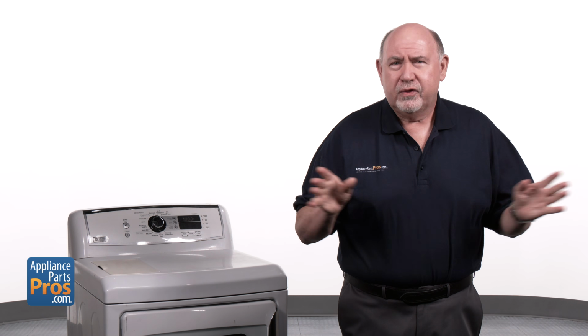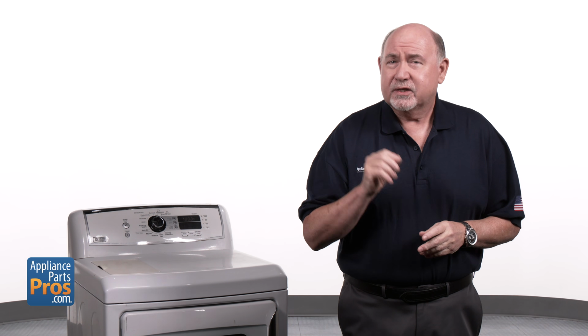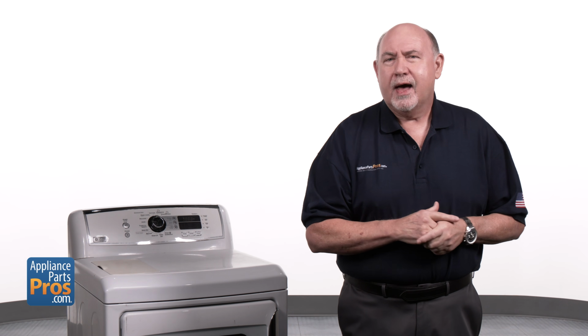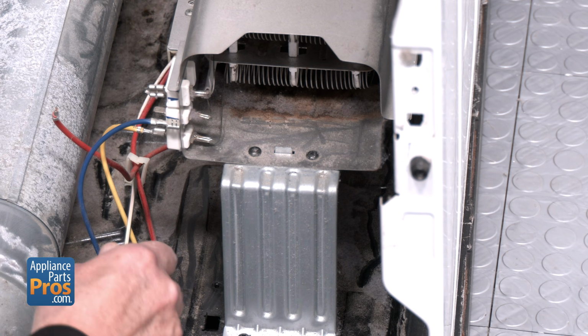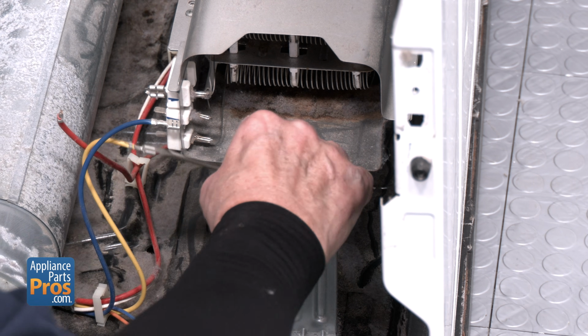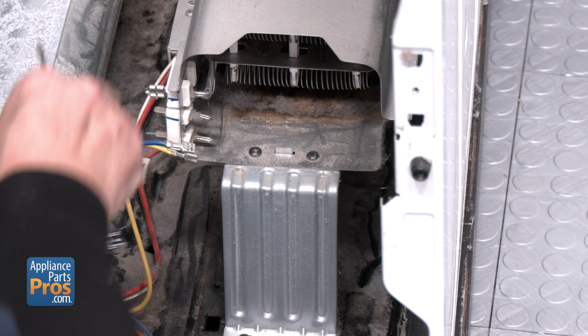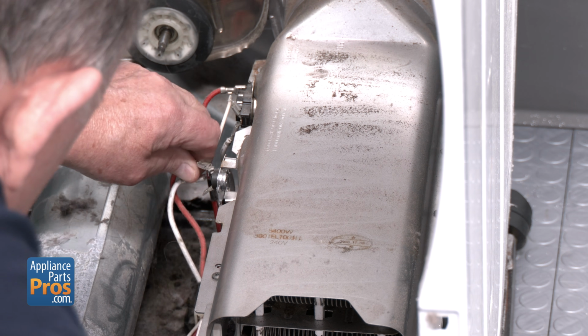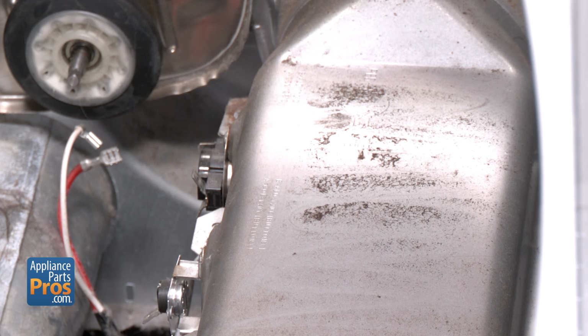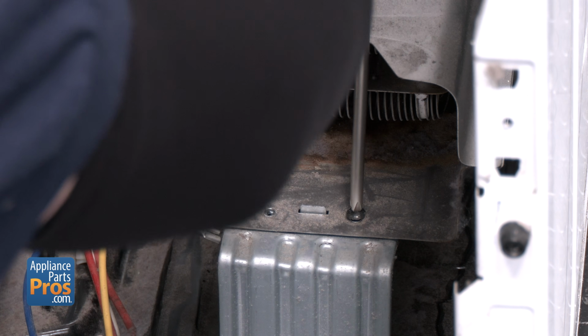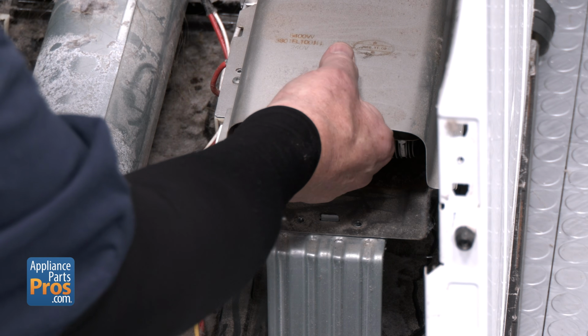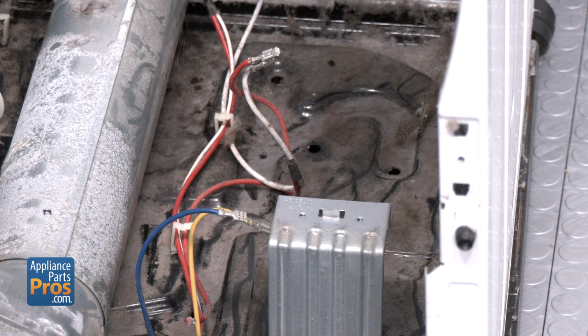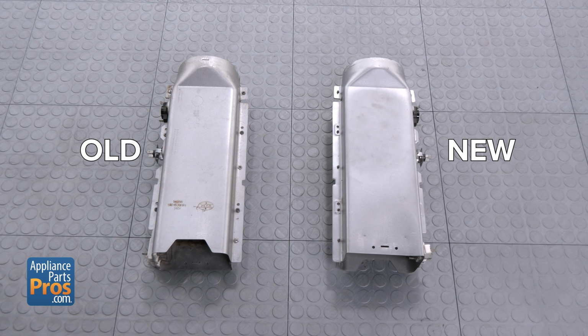After going through all the checks, we found the heating element itself had failed. Let me show you how to replace it. The heating element comes as a complete assembly with the high-limit thermostats already installed. Remove the wiring, take pictures if needed. Then remove the 2 screws in front. Lift up and remove the element assembly. Here's the old element and here's the new one.